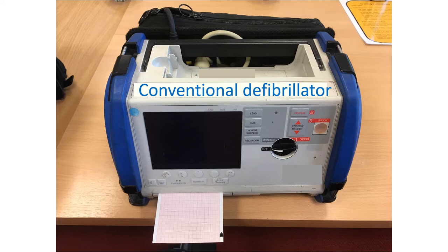Most important precaution during the use of a defibrillator is to keep out of contact with the victim or else you may receive a shock. This may occur even if there is water connecting you and the victim. So, an all clear announcement is commonly used by the operator prior to delivering the shock.